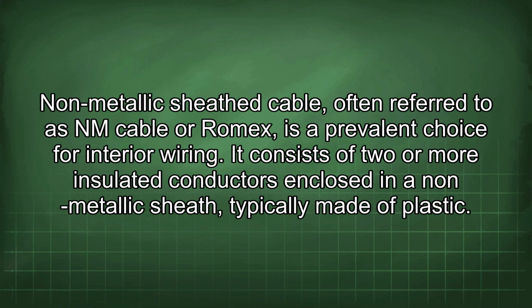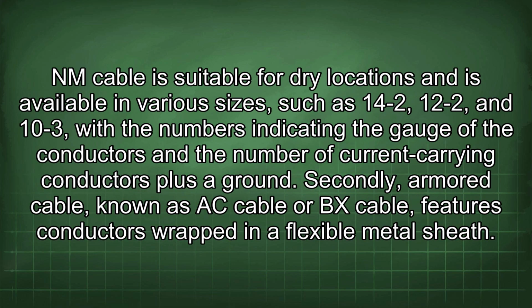Non-metallic sheath cable, often referred to as NM cable or Romex, is a prevalent choice for interior wiring. It consists of two or more insulated conductors enclosed in a non-metallic sheath, typically made of plastic. NM cable is suitable for dry locations and is available in various sizes such as 14-2, 12-2, and 10-3, with the numbers indicating the gauge of the conductors and the number of current carrying conductors plus a ground.